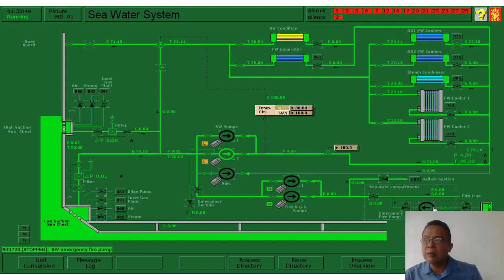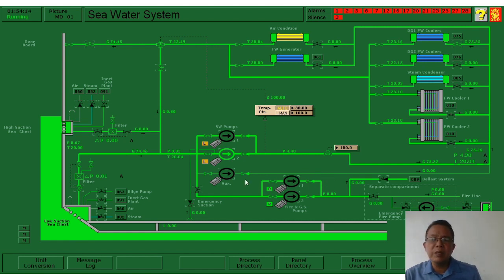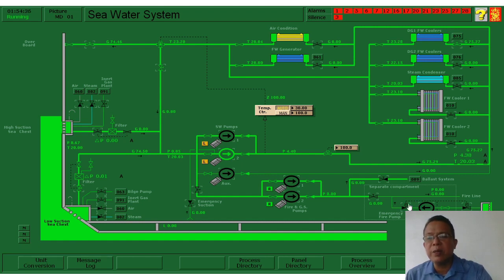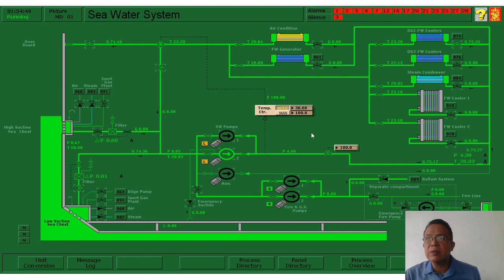The emergency fire pump is smaller than the main fire pump but is sufficient for combating fire in accommodation or on deck. It has a direct suction from the sea. This pump is positioned where any crew member can access and start it — even if the engine room is locked for security purposes at port, the emergency fire pump door can be opened by any crew member immediately. That is why it is called the emergency fire pump.